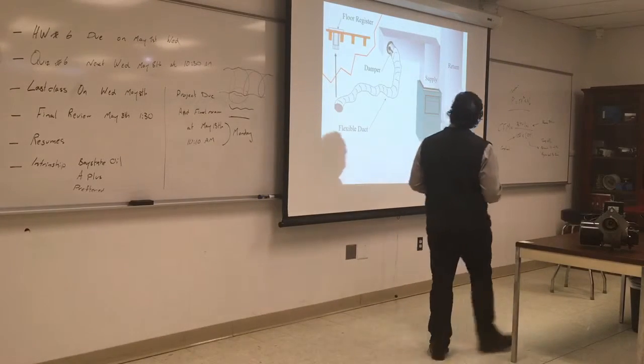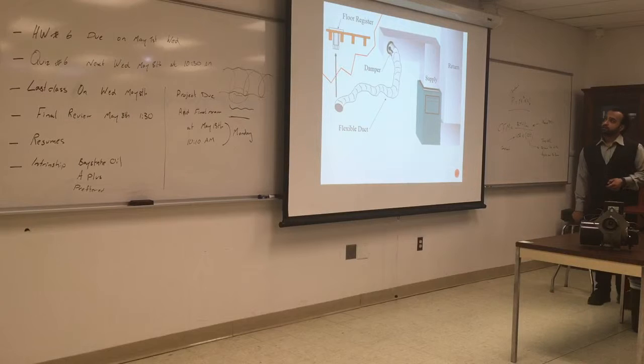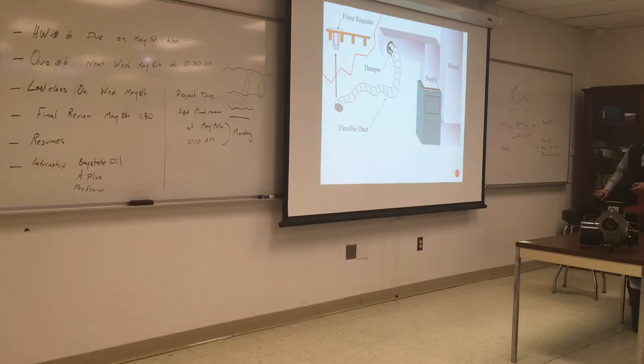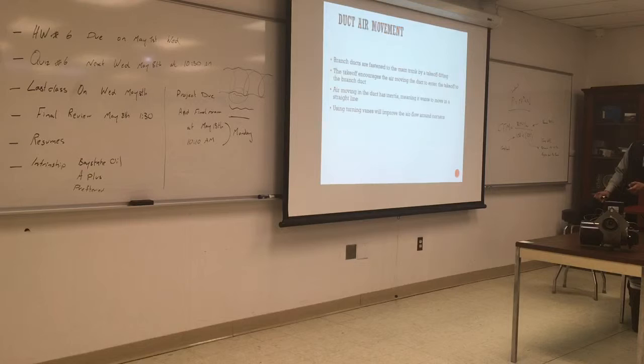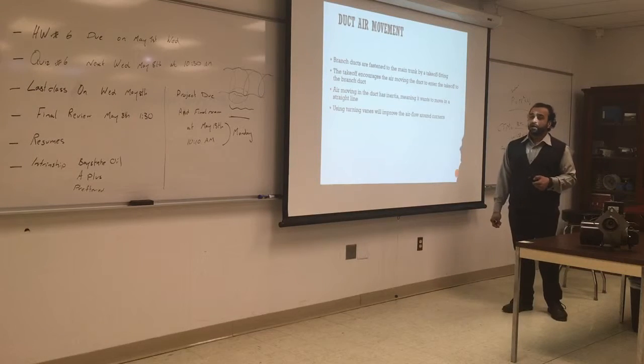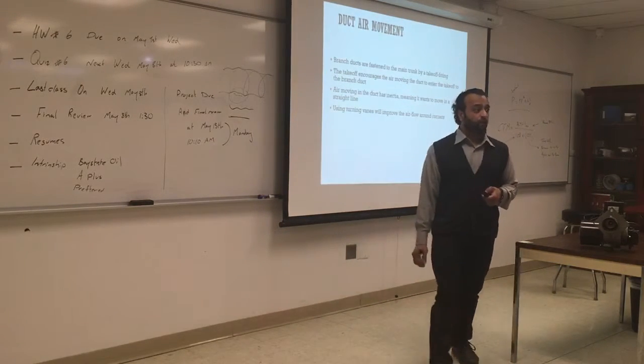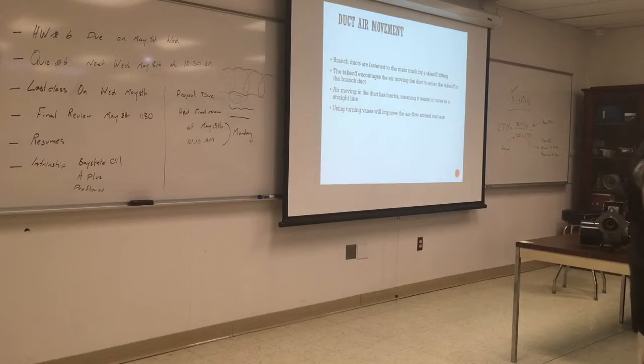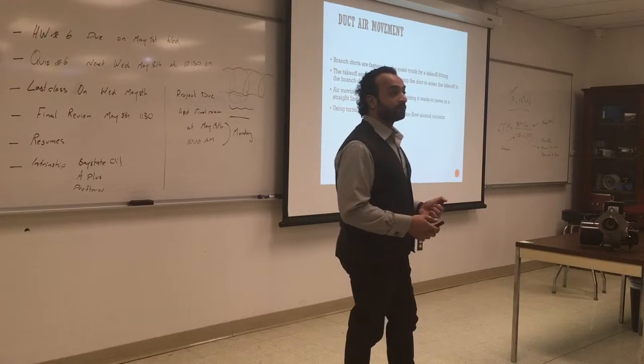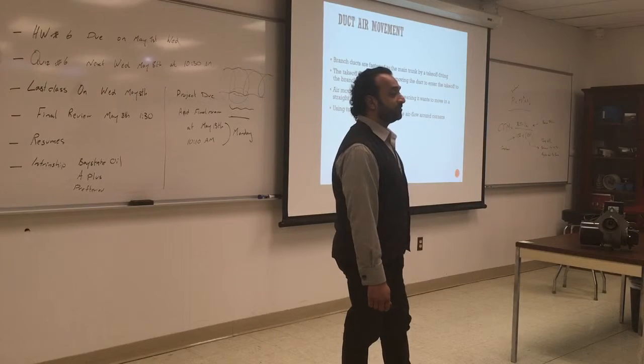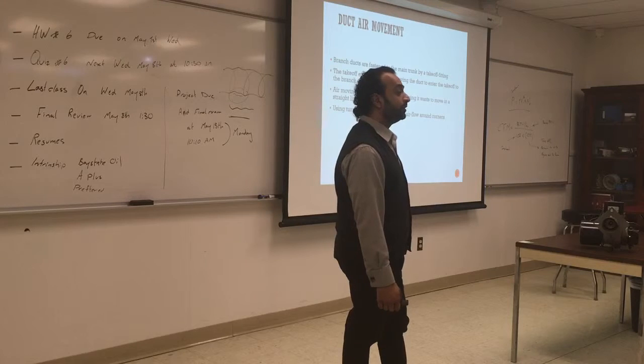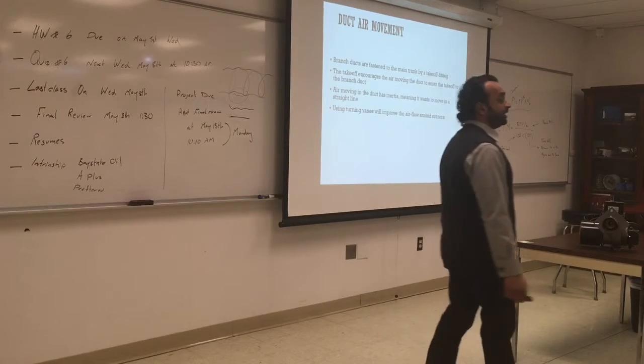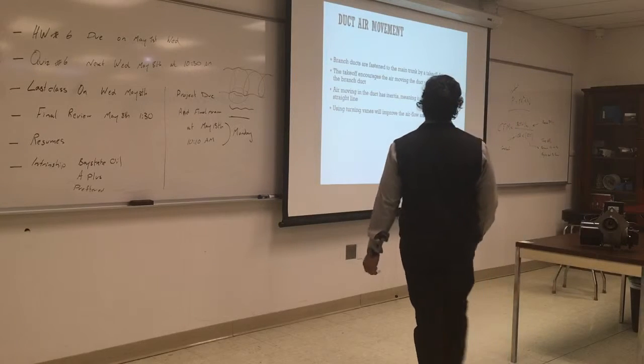So this is an example of flexible duct. This is the supply, the return, and this is where you want to put the floor register. This is my return line over here. Okay. Duct air movement. Branch ducts are fastened to the main branch by a takeoff fitting. Fittings are very important, and if you go to Home Depot or Lowe's, you'll find a lot of fittings specified for each connection, so you don't have to put duct tape all over the place. And by the way, duct tape also comes in different temperature ratings. Don't use regular duct tape on heating pipes, because they get hot, up to 120, 130, and some duct tapes cannot withstand that.